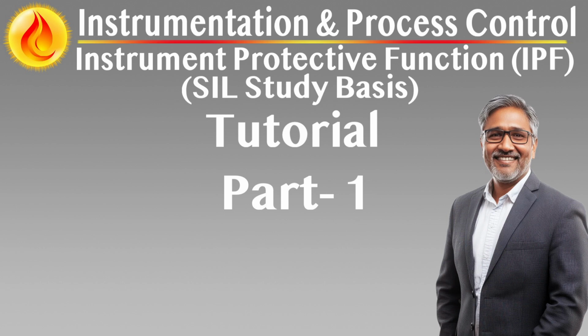Performance-based validation and proof testing. Each IPF must be designed for verifiable performance, with test coverage and diagnostic strategies aligned to its classification. This includes clear proof test procedures and intervals, monitoring of test success rates and failure modes, adjustment of test frequency based on field reliability data, automated partial stroke testing for valves where feasible.